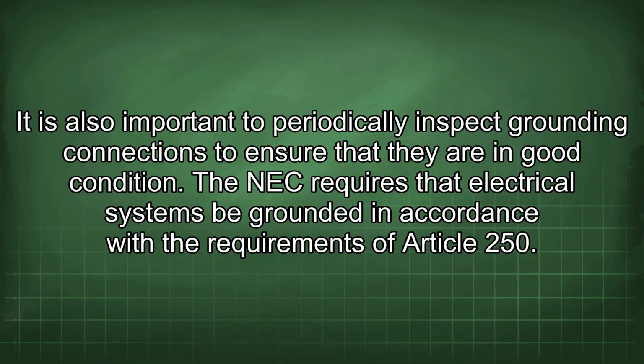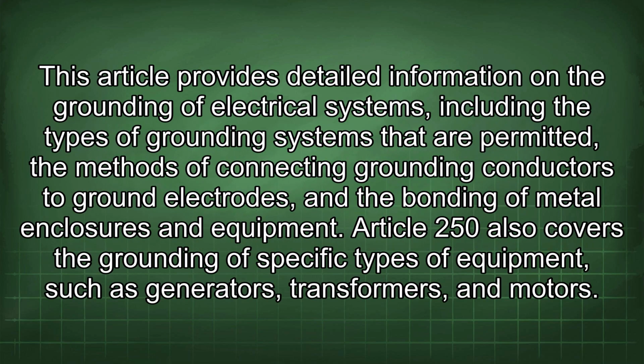It is also important to periodically inspect grounding connections to ensure that they are in good condition. The NEC requires that electrical systems be grounded in accordance with the requirements of Article 250. This article provides detailed information on the grounding of electrical systems, including the types of grounding systems that are permitted, the methods of connecting grounding conductors to ground electrodes, and the bonding of metal enclosures and equipment. Article 250 also covers the grounding of specific types of equipment, such as generators, transformers, and motors.